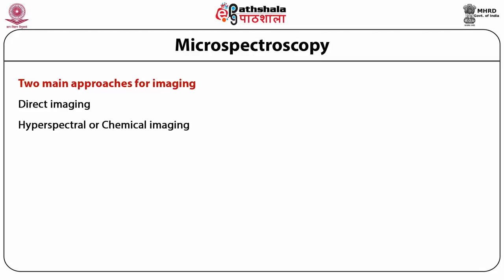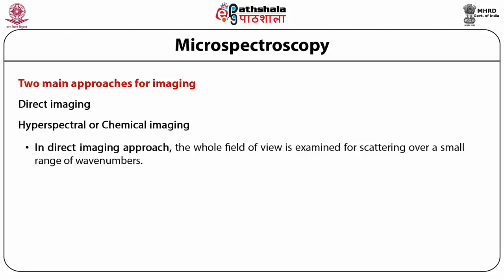There are two main approaches used for imaging with Raman spectroscopy. The first is direct imaging and the second is hyperspectral or chemical imaging. In the direct imaging approach, the whole field of view is examined for scattering over a small range of wavenumbers. For example, a wavenumber characteristic of cholesterol could be used to record the distribution of cholesterol within a cell culture — an extremely sensitive experiment that would be very difficult with other techniques.